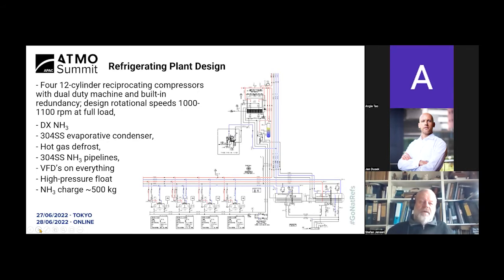And the specific energy consumption there is 60 kilowatt hours per cubic meter per year. So approximately 5 times bigger than the predicted, and approximately 6 times bigger than the actual recorded specific energy consumption. I believe that plant has now been turned off and everything has been moved into the new facility. And the older facility is used for higher temperature storage.